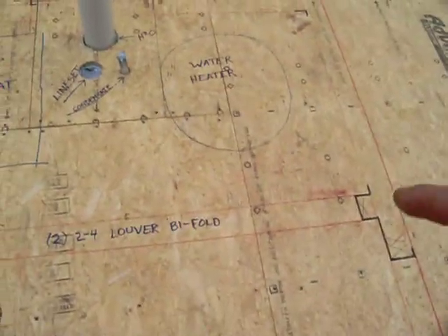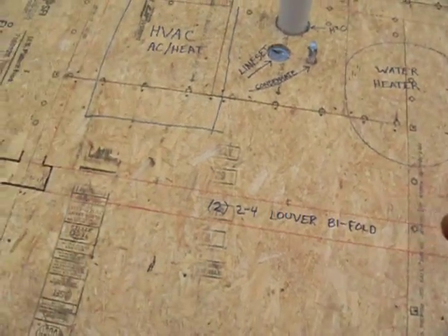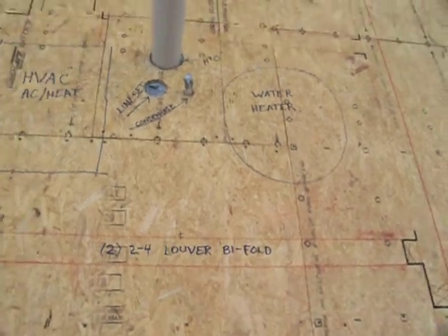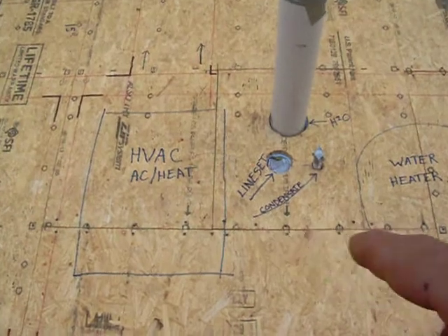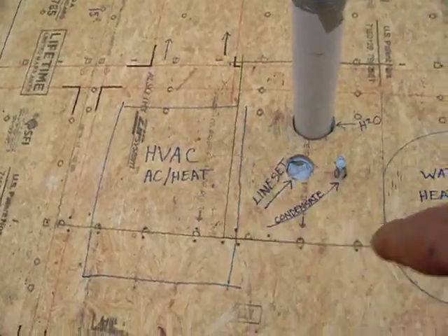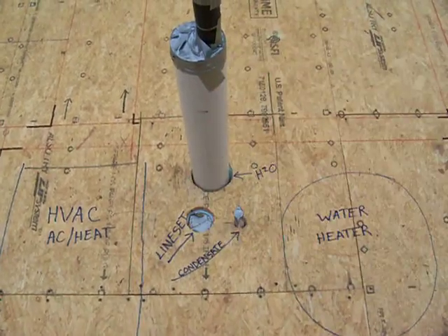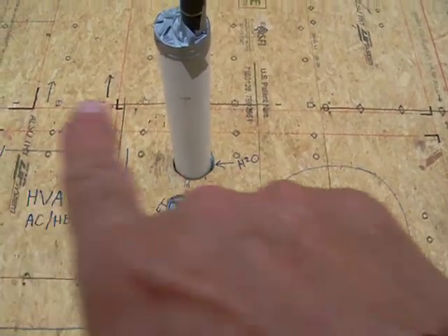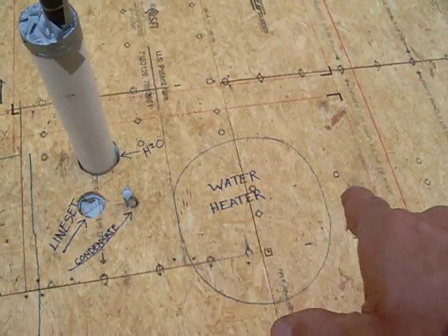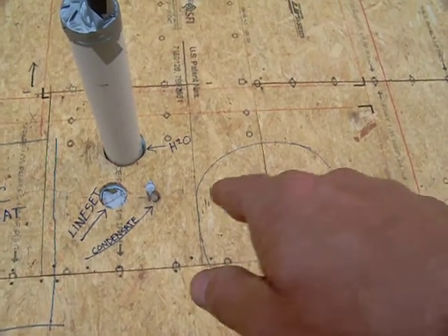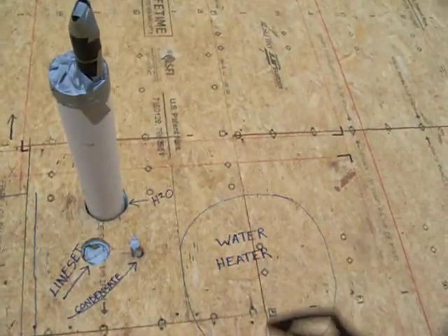I've got two two-foot-four louvered bi-folds so the HVAC can breathe. Pretty self-explanatory: HVAC line set for the refrigerant lines comes out and goes under the slab out the side. This is my condensate line, which will drip water into that. I'll tie a pan underneath the water heater so that if it ever blows out, it'll hit the pan and run into my condensate line, my one-inch line, and discharge out the building and not on the floor.